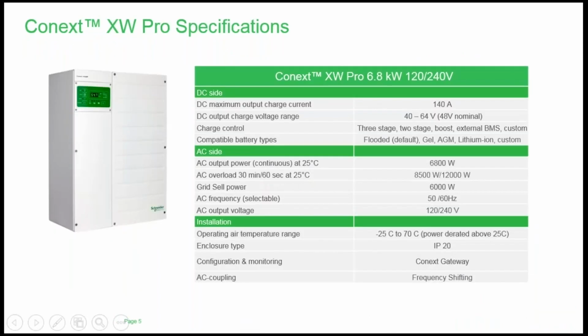Specifications for the XW Pro: 140 amps DC, 48 volt battery bank exclusively. DC input range 40 to 64 volts. We offer 3-stage charging, 2-stage charging, and boost charging for flooded lead acid battery types. We have external BMS communication capability and a custom battery menu. Our output power is 6.8 kW at 25C. We have a very robust surge capacity, which is 8.5 kW for 30 minutes, and a full 12 kW for 60 seconds.